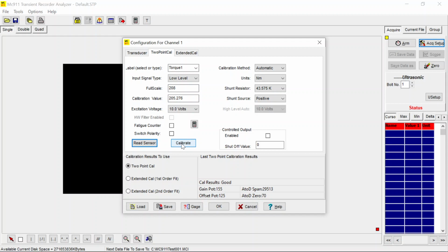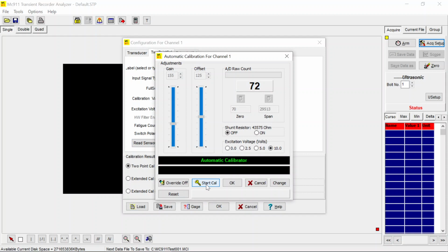So go calibration. Calibrate, and we apply the same load as before. We're reading 204. Before we were reading 202, now we're reading 204. So these two are matching. So that's a method to change the A to D using another instrument's number to match our two systems together.